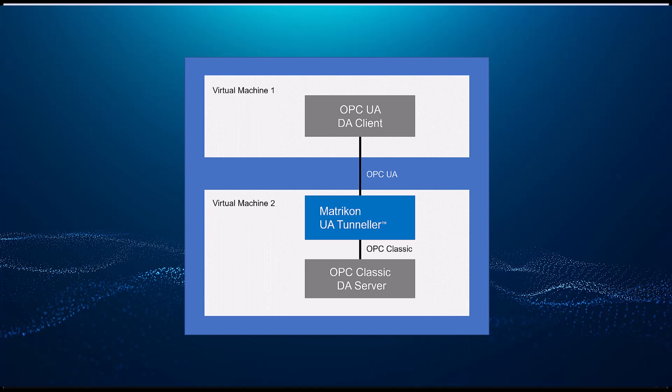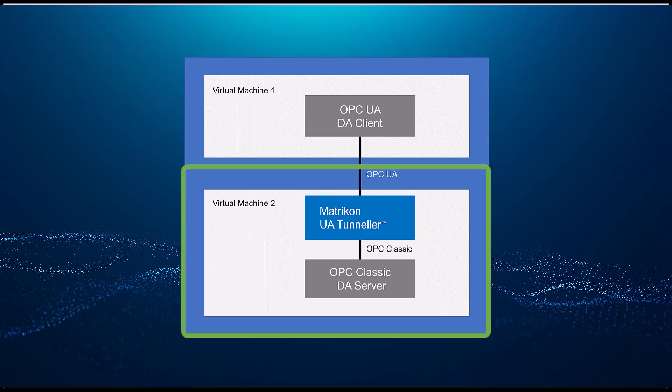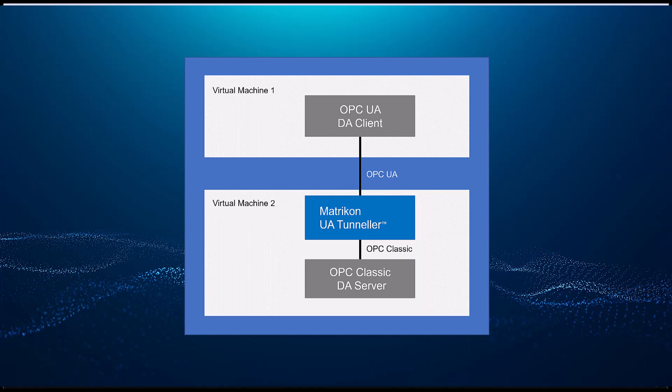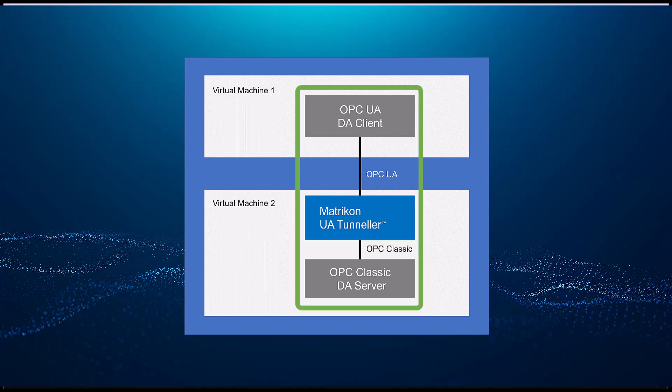For this demonstration, I'll use two virtual machines. One will have the OPC UA client on it, and the other will have the classic OPC DA server on it. Because we want to avoid remote DCOM connections, I have the Matrikon UA Tunneller already installed on the same computer as the classic OPC DA server. The OPC UA client will connect to Tunneler remotely over a single TCP port, and Tunneler will convert OPC UA to DA and then connect to the classic OPC DA server locally.